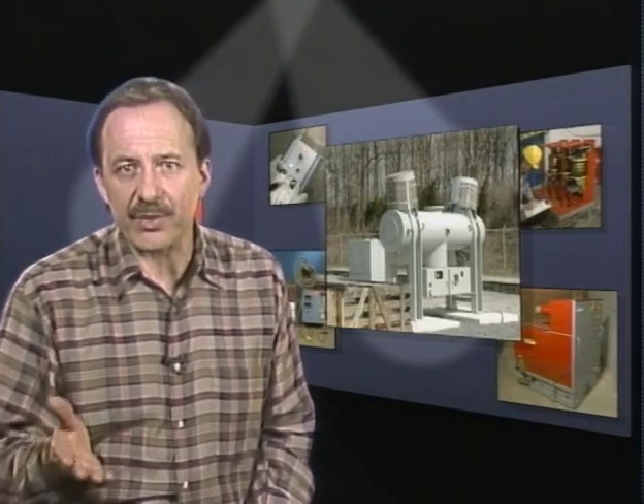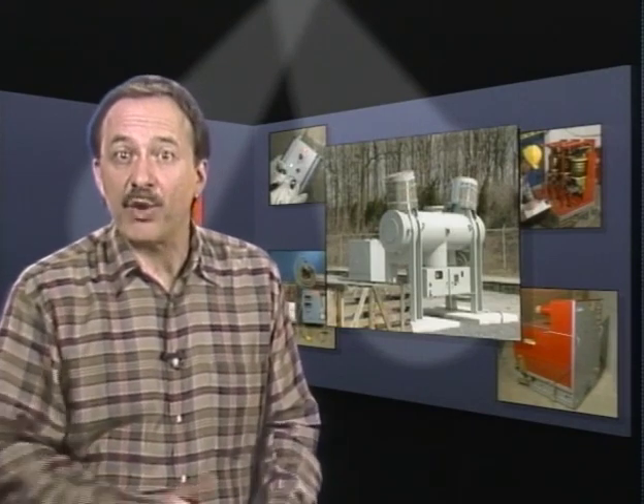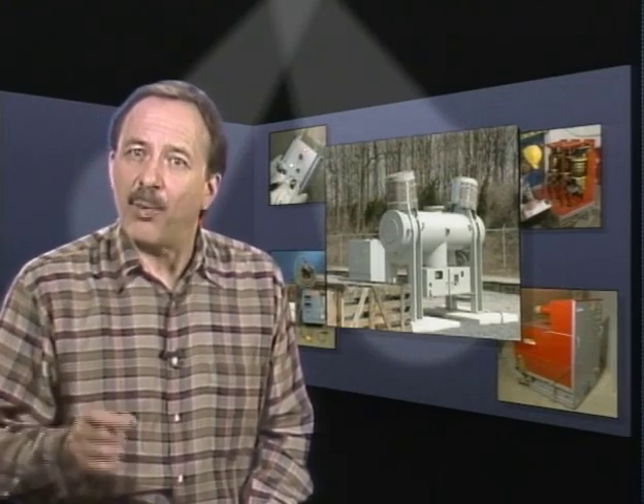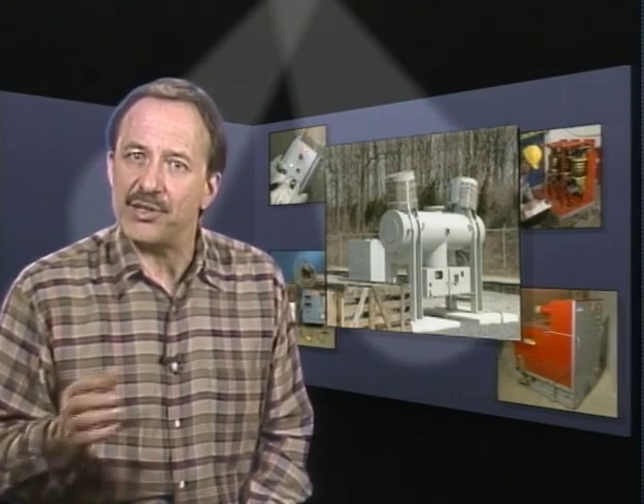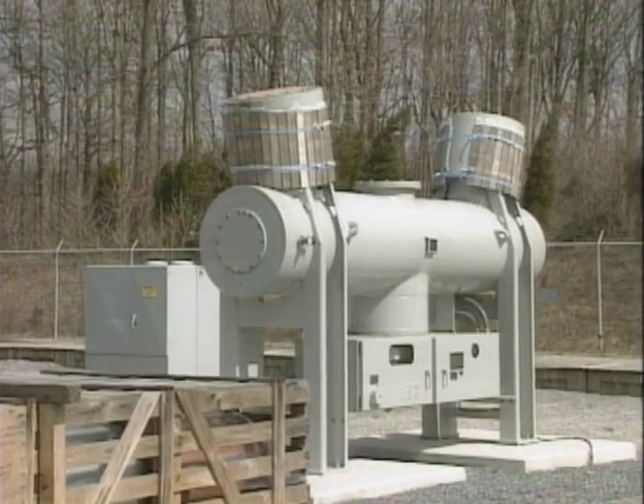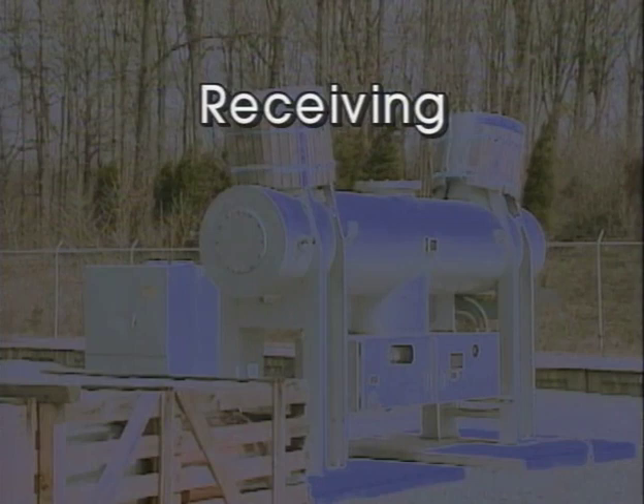Now, a new circuit breaker can be a breaker that's been shipped directly from a manufacturer. In this case, the breaker is thoroughly inspected and tested at the factory before it's shipped to the customer. But a new circuit breaker can also be a breaker that's been accepted from another source, such as another utility or an equipment broker. It may or may not have been recently inspected and tested. But regardless of whether a breaker is new from the manufacturer or new from another source, it's important to make sure that the breaker wasn't damaged during shipping and that the breaker is properly installed, inspected, and tested before it's put online. In this part of the program, we'll look at the steps involved in receiving a new circuit breaker.